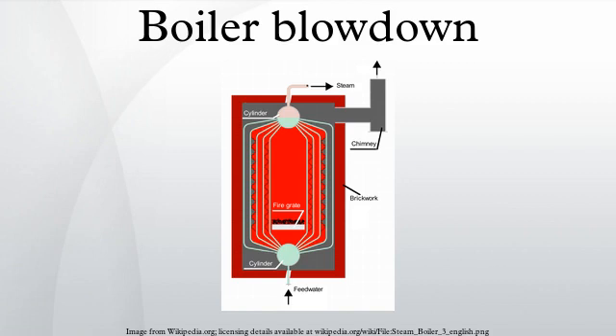Boiler blowdown is water intentionally wasted from a boiler to avoid concentration of impurities during continuing evaporation of steam. The water is blown out of the boiler with some force by steam pressure within the boiler. Bottom blowdown used with early boilers caused abrupt downward adjustment of boiler water level and was customarily expelled downward to avoid the safety hazard of showering hot water on nearby individuals.